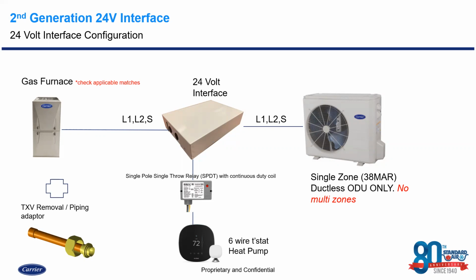In this case, now we've got a gas furnace. And of course, we want to check the applicable matches for the systems. We still need our TXV removal or our piping adapter. But now what's changed on here is that we need a single pole, single throw relay with a continuous duty coil, of course, because we have that dual fuel operation between gas furnace and heat pump. And now we need a 6-wire thermostat set up as a heat pump because we have that dual fuel operation. We'll get into that wiring in just a few minutes.